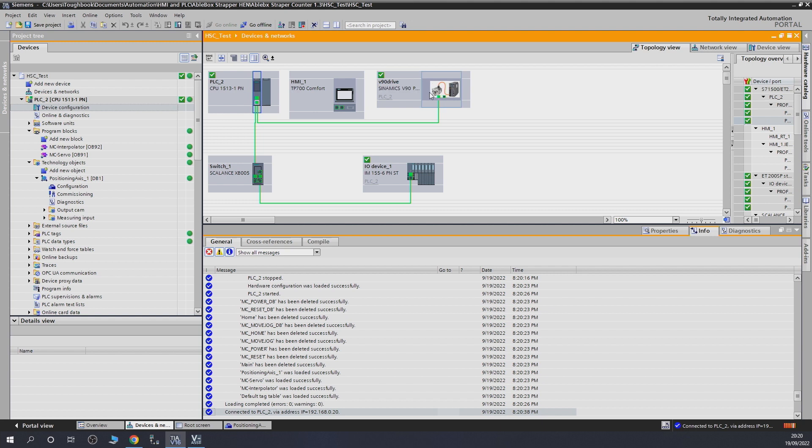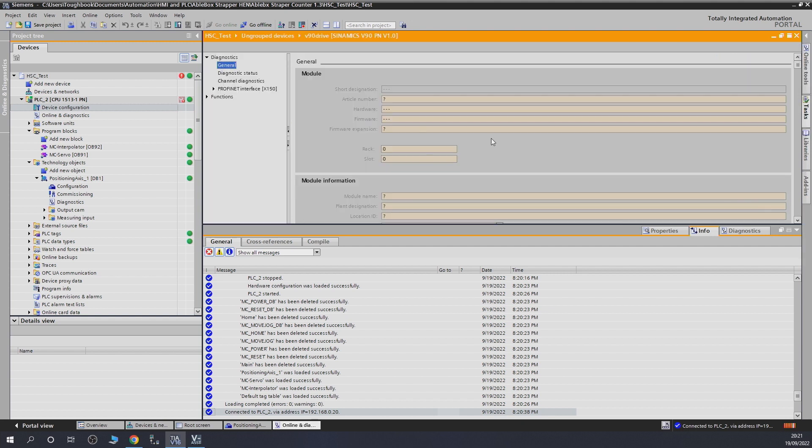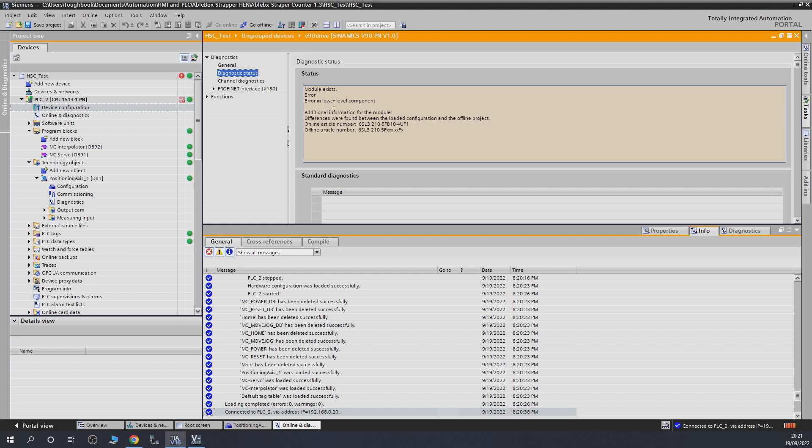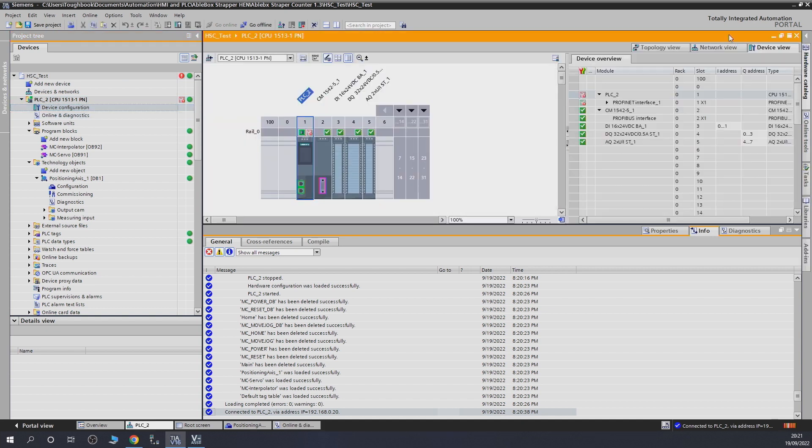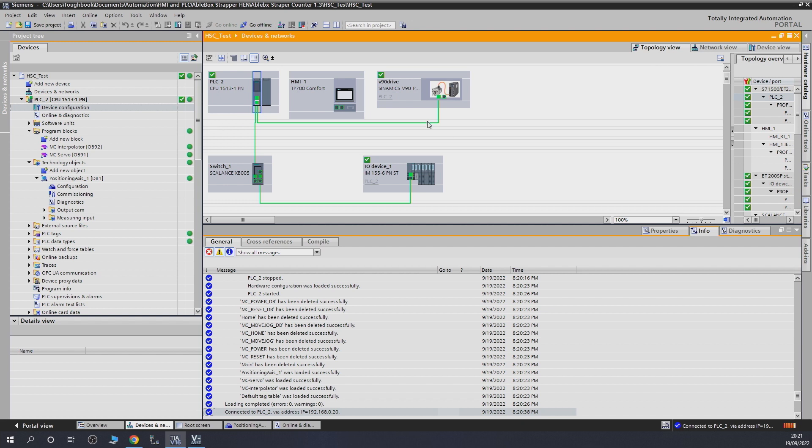Okay, everything is working well. Look what happens when I unplug my drive. As you can see, now it becomes red. That's where the topology is really good. I'm going to plug it into P2. See, I plugged it into P2 and it doesn't do anything because it says this is not how my topology is set up. It says I'm reading it, I'm happy. But let's see what it says in diagnostics. In low level components, additional information, see, it's configuration, it's got a problem. It says it's not talking to the correct topology port. That's very important that the topology is set up correctly. Let's unplug it and see if it fixes the problem. My drive is actually saying F1912. I would show you guys, but my camera is focused on our linear actuator at the moment. Technically, if all goes well, as you can see, it's going to get green in a minute and fix itself up.